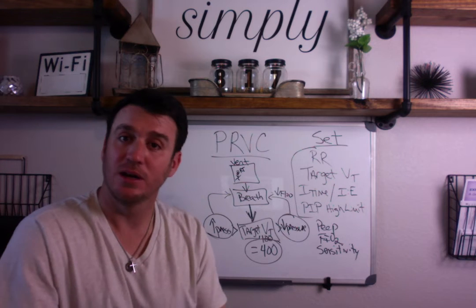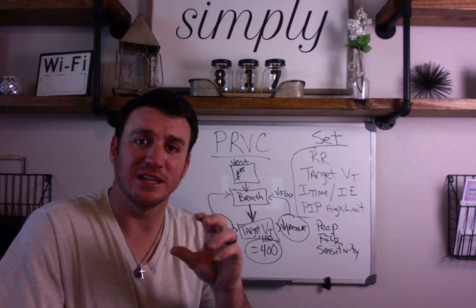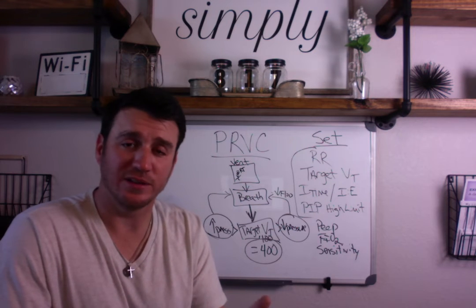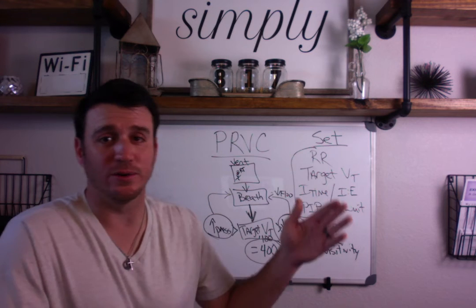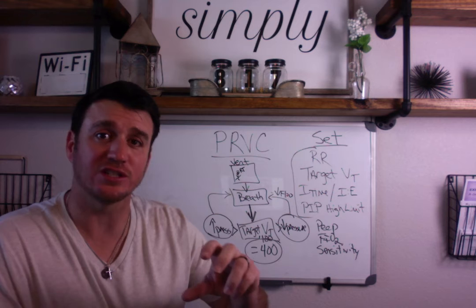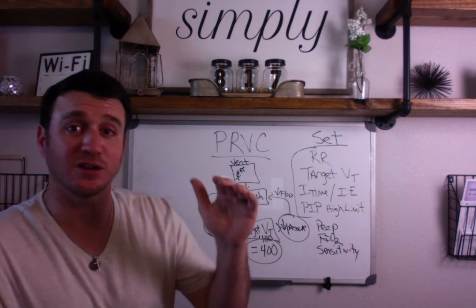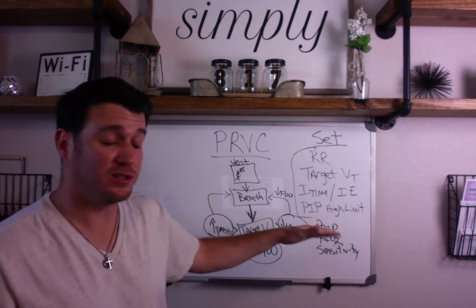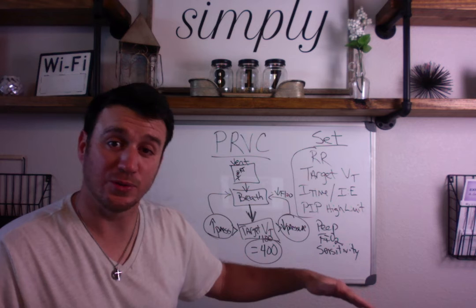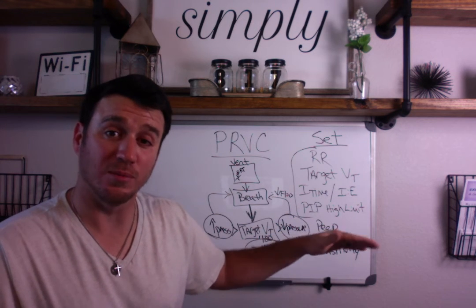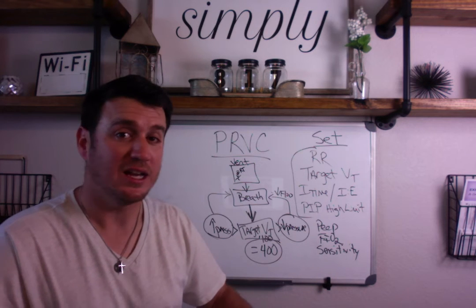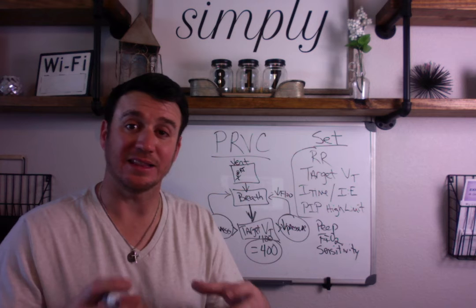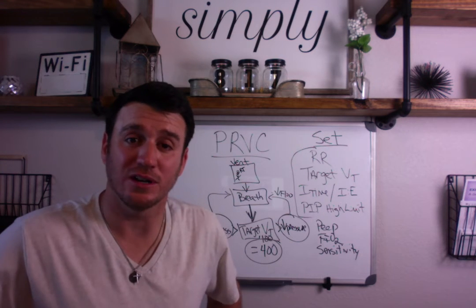The ventilator is literally adjusting every single breath relative to the previously exhaled breath. If the previously exhaled tidal volume is too low, it increases pressure by automatically adjusting flow upward — increasing flow increases pressure, increasing volume delivered, getting closer to the target tidal volume. If volume comes back too high, pressure is decreased on the next breath by decreasing the variable flow. This continues until the target tidal volume is achieved and held, mechanically ventilating the patient at that setting.